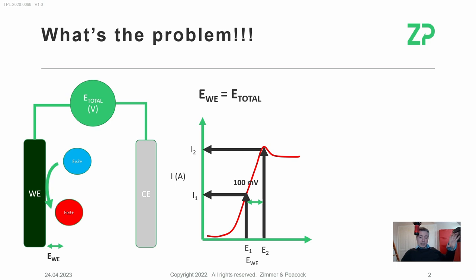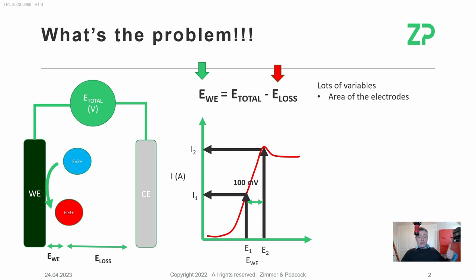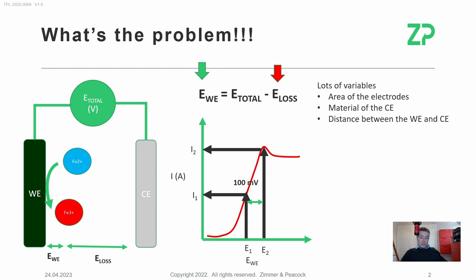There are many parameters that cause a variation in that potential loss. The area of the electrodes — if we use a big counter electrode, the potential lost at the counter electrode is less; if we use a small counter electrode, we can get big losses. The material of the counter electrode — whether you're using platinum, gold, or carbon — can give very different losses. The distance between the working and counter electrode is one of the more sensitive parameters.